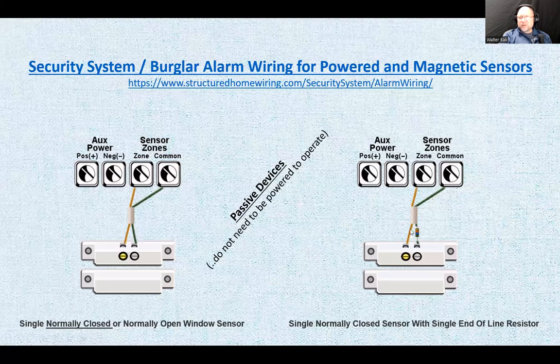Now, some boards can be programmed so that you can connect 2 of those onto one zone. So you can have 2 separate zones. One is going to be a closed loop, so 0 ohms, and the other one is going to be connected as the end-of-line resistor. So you have to tell the system to work that way, and in that way you can double the zones.